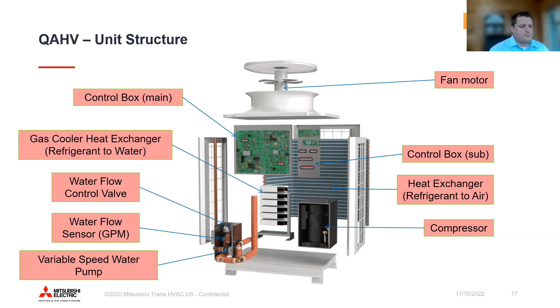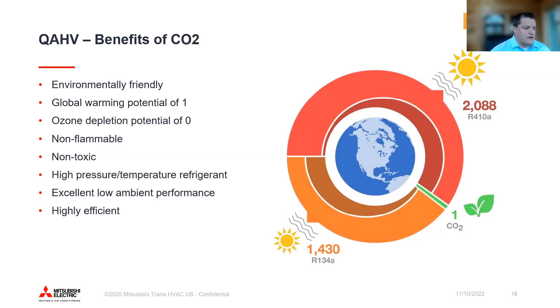So like we talked about, GWP of 1, ozone depletion potential 0. If you look at today using R410A, 2088 for GWP, and then a lot of comparables today, those multi-pass products are in that transition phase of switching from R134A to a different refrigerant. There are various options out there, but it's still going to be a fairly high GWP. And this is all coming into play as we get closer to some of the GWP regulations to meet below 750 come 2026.